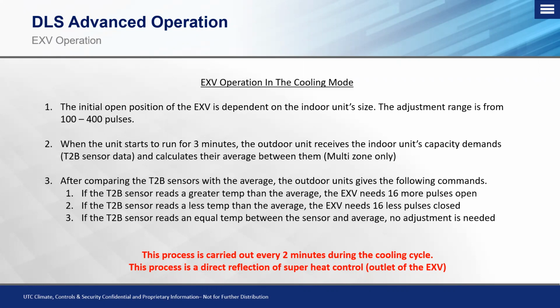When a unit starts to run for 3 minutes, the outdoor unit receives the indoor unit's capacity demands, or the T2B sensor data, and calculates between all the zones that are connected. So if you have zones A through C connected, it's going to take an average between the T2B sensors on zones A, B, and C, and then generate an average after a certain amount of runtime. And that's going to be the target angle or the target pulse or the opening position of that EXV to maintain a minimum, or where they're going to go and rest at.